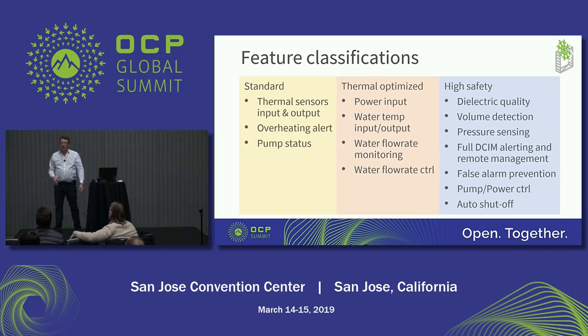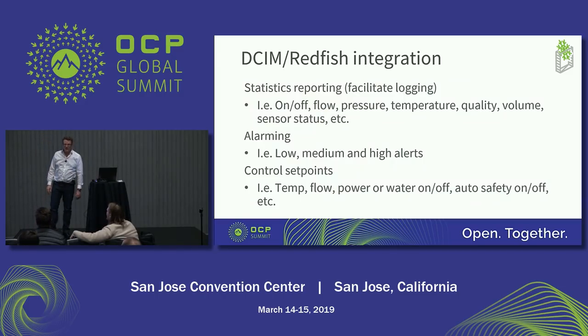But you have to do a lot of effort. You have to really try hard to get into any danger level. Air has a dielectric strength of 3 kilovolts per millimeter. To get down to that level with any of the dielectric liquids, I've tried. I've not succeeded. And I've tried really hard. That's trying to get it down to 3 kilovolts, and the lowest I've been able to get it is to 16. That's by really polluting the liquid.